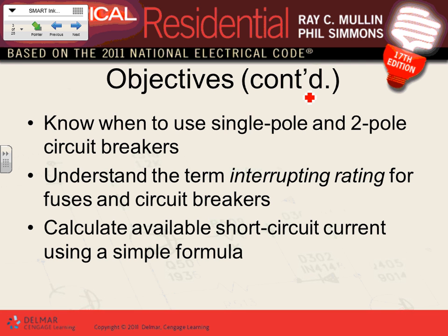Can I have a thumbs up? 99% of the time, guys, when they say a pole, they mean a phase. So three pole means three phase, but it doesn't have to be. It could be two phase and neutral, and I'm disconnected. So here's a two-pole circuit breaker. Can I use this one to disconnect a three-phase system? No, because it's not a three-pole. So there are some regulations. In residential, you have a single pole, you are stuck with these two. Single pole, you guys are familiar with the single pole, just one hot, and two pole. So we'll talk about this one.